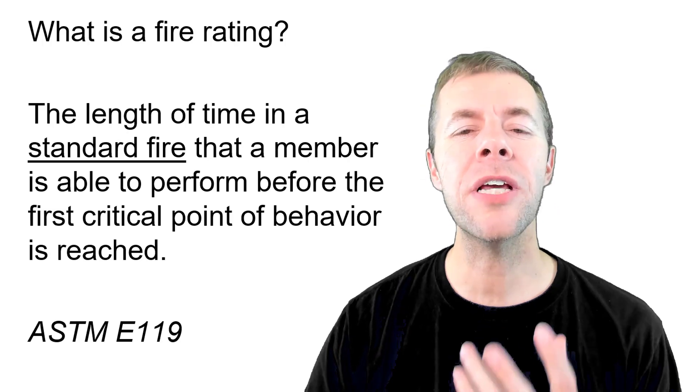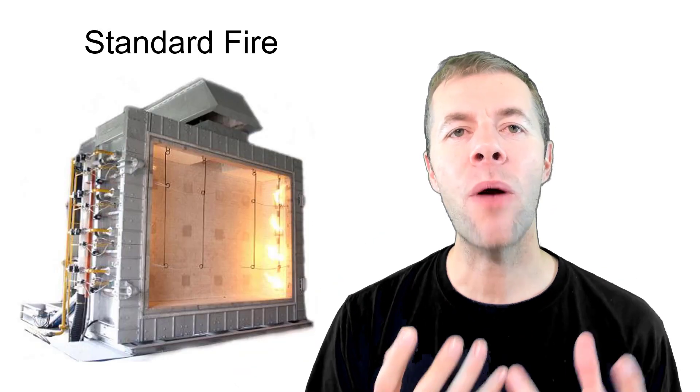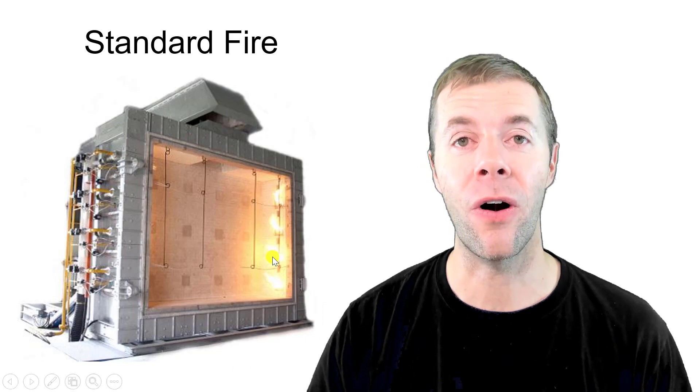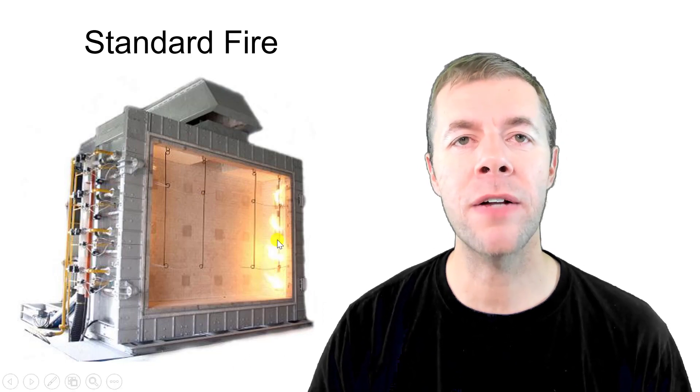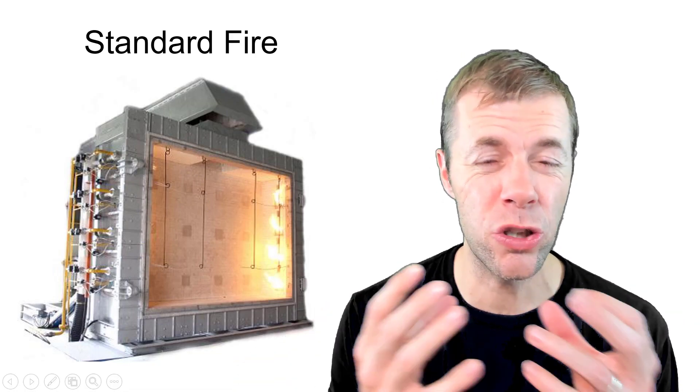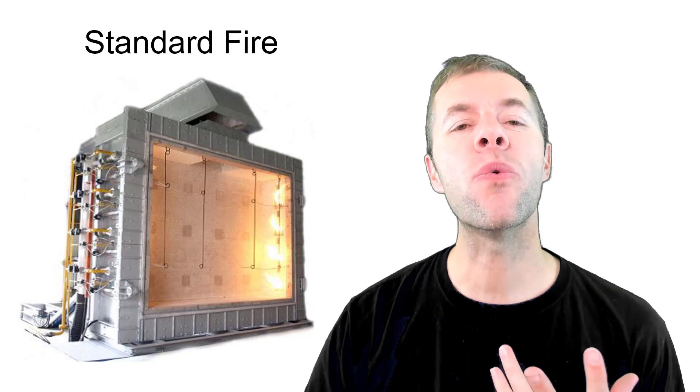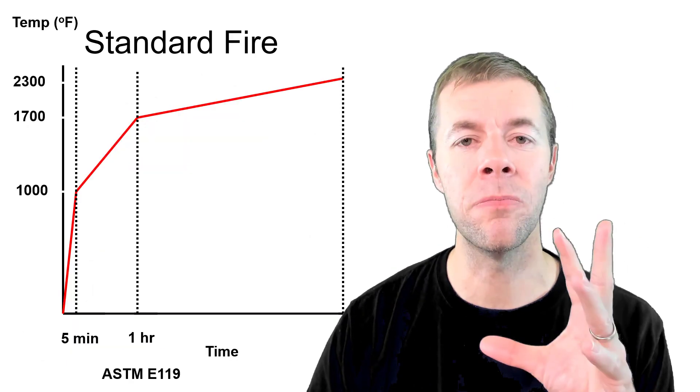Well, ASTM E-119 has you build a special room and in that room you have fire on one side and then you build some kind of structural system. On the opposite side they measure stresses and strains and temperatures of what happens and in that room they subject that system to this temperature.